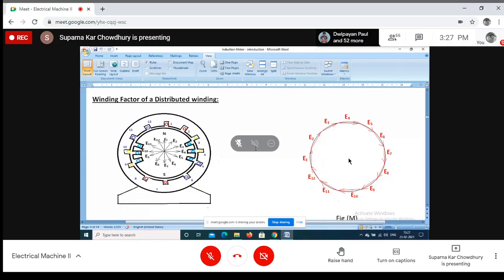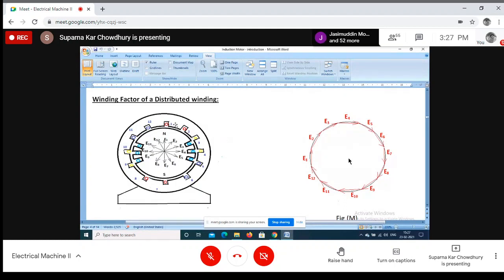Next is winding distribution. The armature winding shown so far has been concentrated, but it is not possible to concentrate all turns of a large armature winding in one slot - the slot would be huge and we would not be utilizing the total machine periphery. So the turns are distributed - there are a number of slots on the stator surface and the windings are distributed over them. For explanation, 12 slots are shown, each with a single conductor.